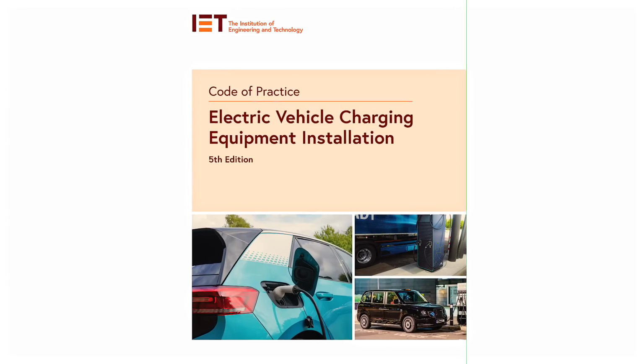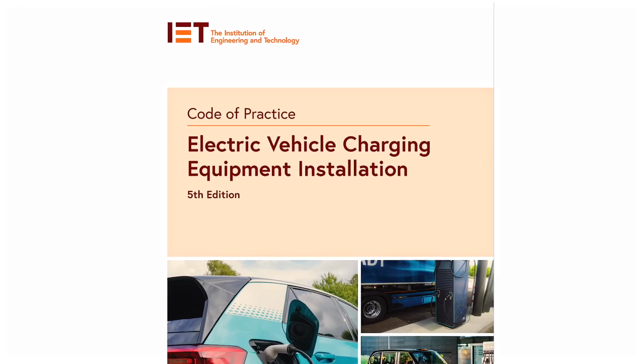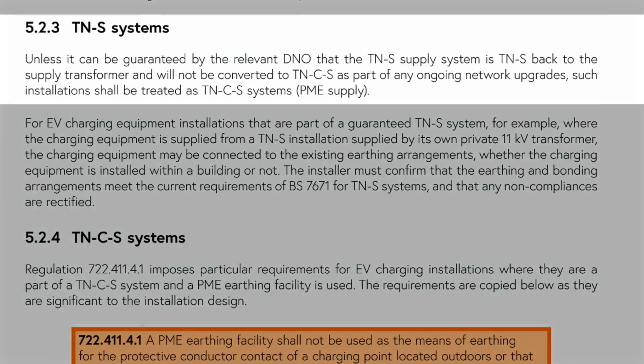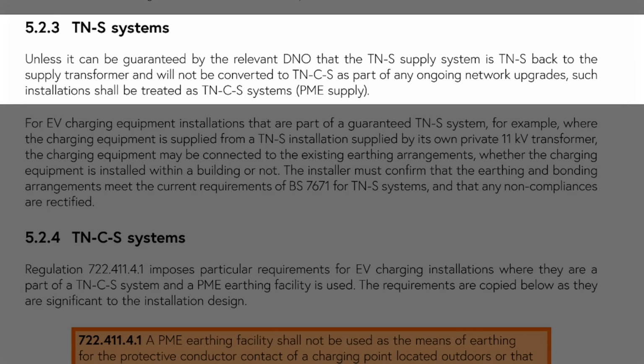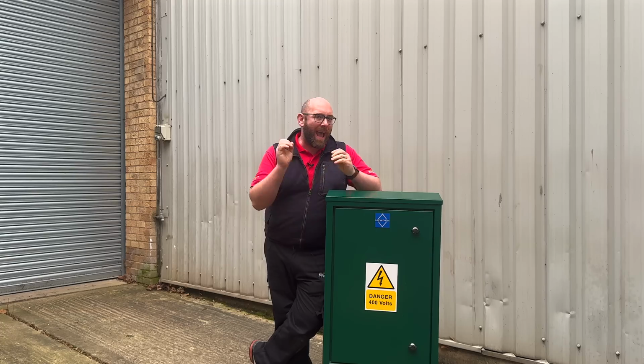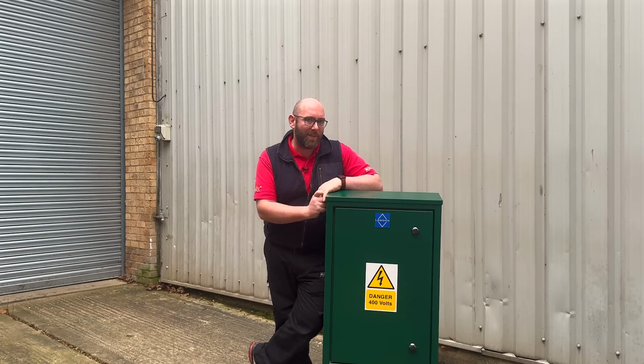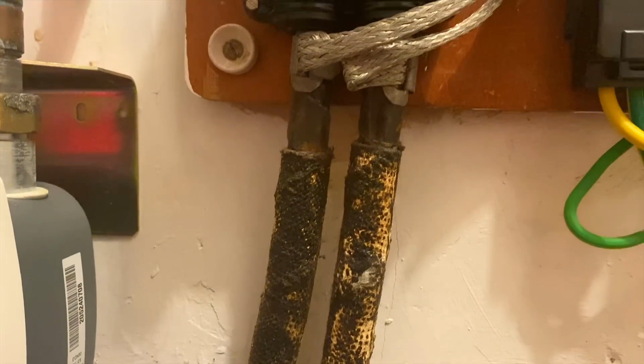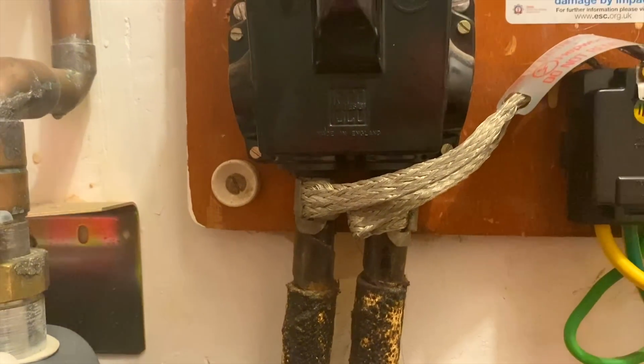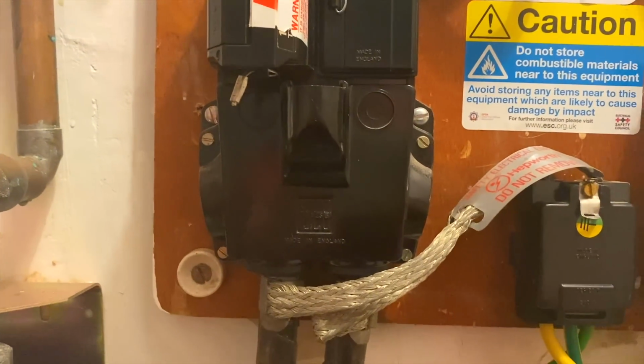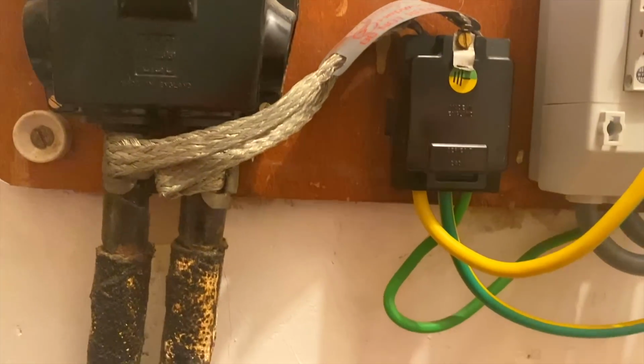Well, the code of practice for electric vehicle charging equipment says that if the system is TNS, we can rely on the earthing method as long as we have it guaranteed that the separate earth goes back to the supply transformer. So how are we going to be able to guarantee that? Well, most of the time you can't, and this is because it's common practice to convert older TNS systems into TNCS, and not just at the supply intake.